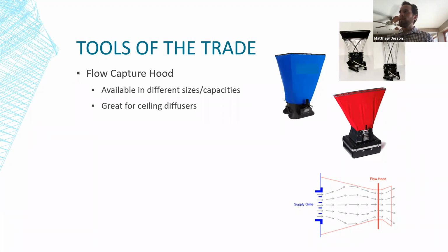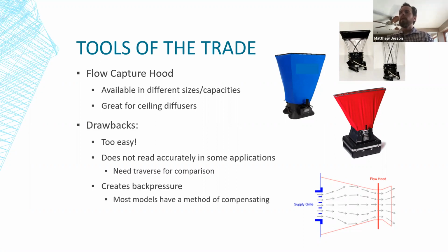And the clear hoods that you see in the top right, that's actually a lower flow hood that's better at capturing low CFM values. And it has two different tops that it's showing. Drawbacks to the hood, first of all, it's just too dang easy. And I'm only partially joking about that. It is so easy to use that it can give you kind of a false sense of security. We'll talk in much more detail about that later.